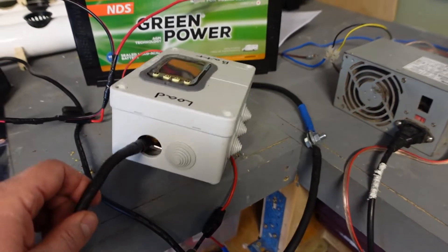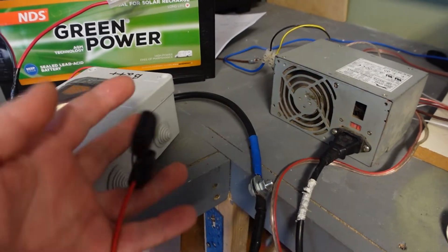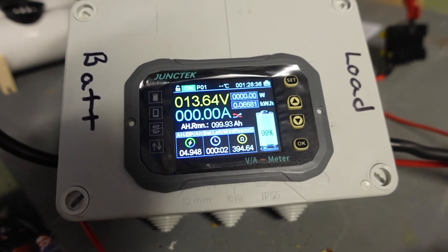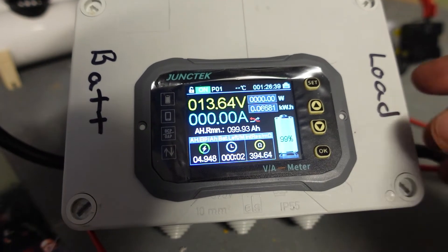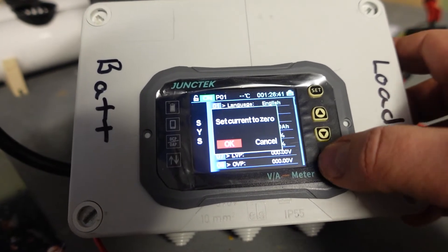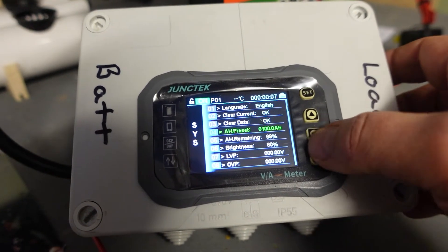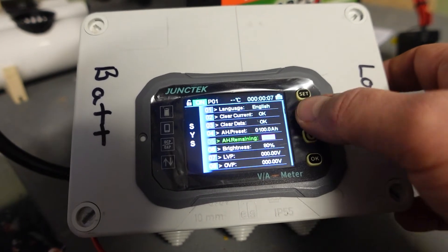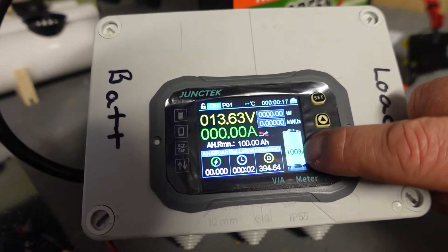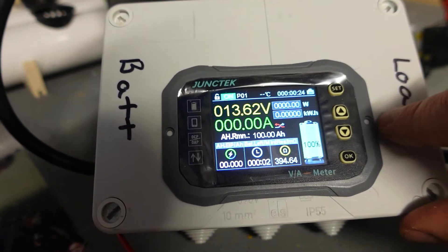Just to point out, this is my new box that I've made up for it. The shunt is inside the box with the control module and I've just got a negative lead coming out and a positive to be able to charge it up. I've got everything connected up again. Going to show the setup - go to clear current, click OK, move over to OK and click OK, then clear data, OK again. Make sure this is set remaining at 100. So we're now showing 100 amp hours remaining, 100 percent.